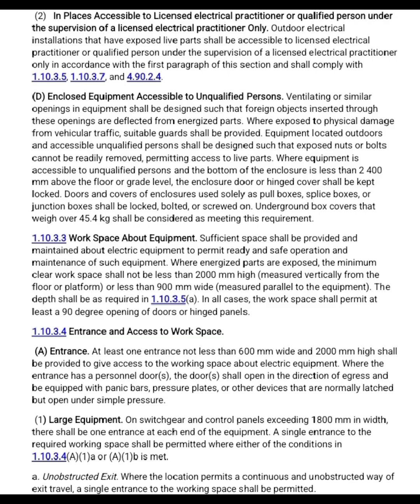1.10.3.3 Workspace about equipment. Sufficient space shall be provided and maintained about electrical equipment to permit ready and safe operation and maintenance of such equipment. Where energized parts are exposed, the minimum clear workspace shall be not less than 2,000 mm high, measured vertically from the floor or platform, or less than 900 mm wide, measured parallel to the equipment. The depth shall be as required in 1.10.3.5a. In all cases, the workspace shall permit at least a 90-degree opening of doors or hinged panels.